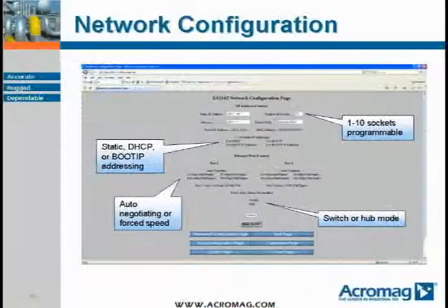As with other Acromag modules, the ES2161 and 62 modules are configured and set up through a simple web interface using your computer's browser, so there's no need to install or maintain any software. The ES2161 and 62 modules support up to 10 sockets, meaning each module can handle up to 10 masters, allowing 10 concurrent users to talk to the device. The number of sockets allowed is programmable as well, allowing the number of masters to be limited to just one or a few for added security.